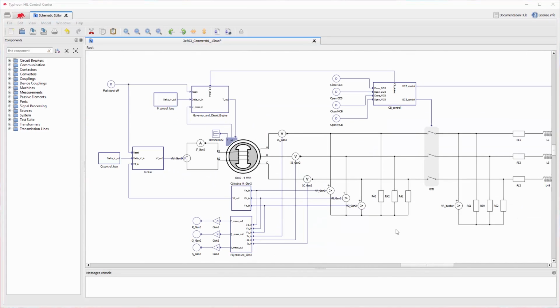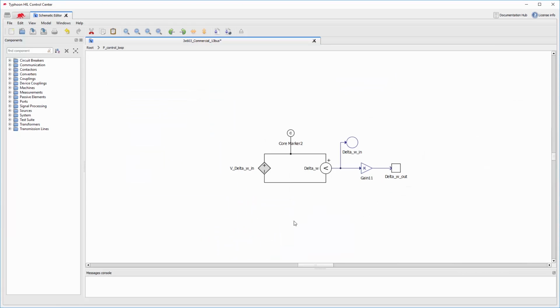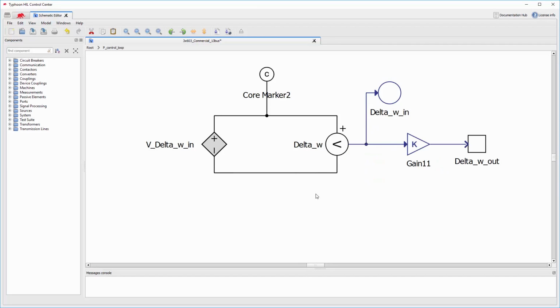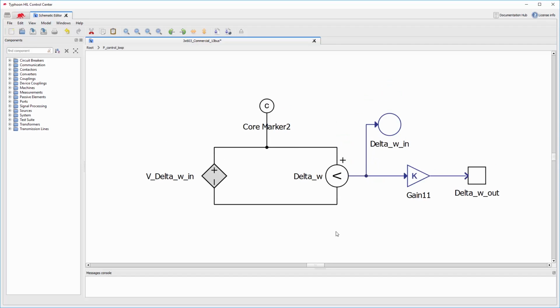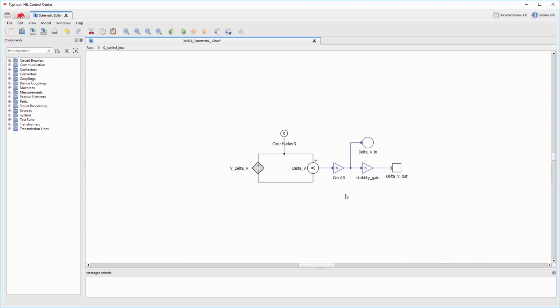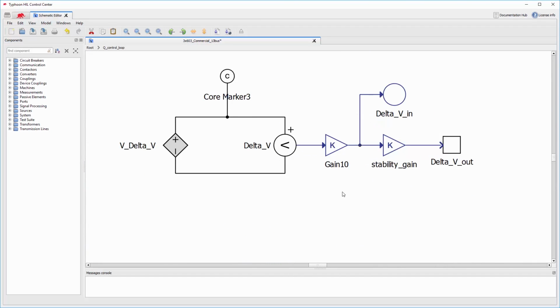Gen 2 does not have the secondary loops implemented in our software, since the external Woodward EasyGen 3000 controller is the one responsible for that. In our schematic, we only have to use an externally controlled voltage source to receive the information sent by the controller and send small voltage deviations to the exciter. Another externally controlled voltage source is used to send small deviations in speed to the governor.